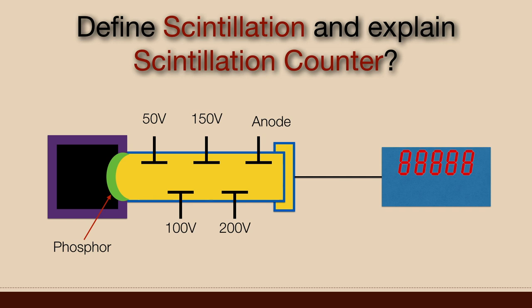The surface of photocathode is coated with cesium and antimony alloy. The dynodes are connected in such a way that each dynode is at a more positive potential than previous one. Thus, the electron beam traveling from one dynode to the other is continuously accelerated.